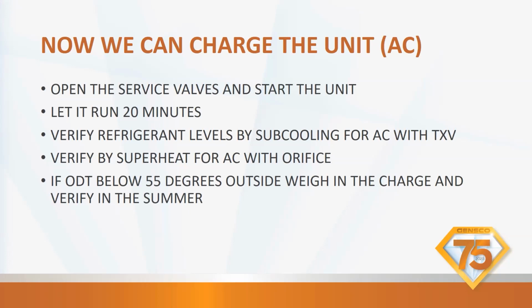Remember, these units didn't get built yesterday. They were built weeks or months ago, and then they get shipped to us. And by the time they go to our office, your office, everything, if it still has refrigerant in it, it probably does not have a leak, okay? So the oil in the bottom of those units could be just from when they charge it, because the way that they charge them now is they have these jigs that they set up and they actually put it into the service ports where you're going to solder in your pipes.